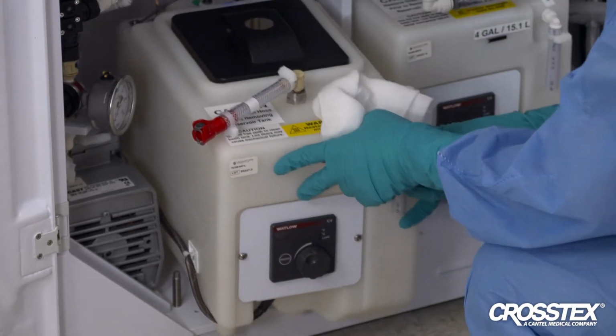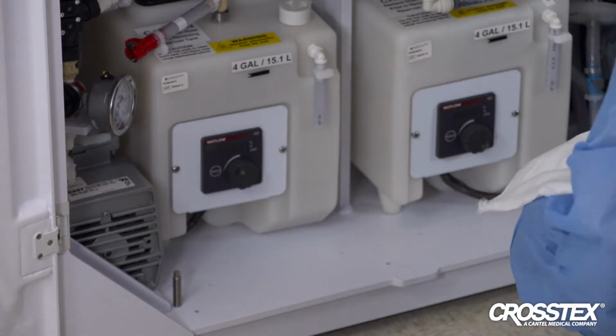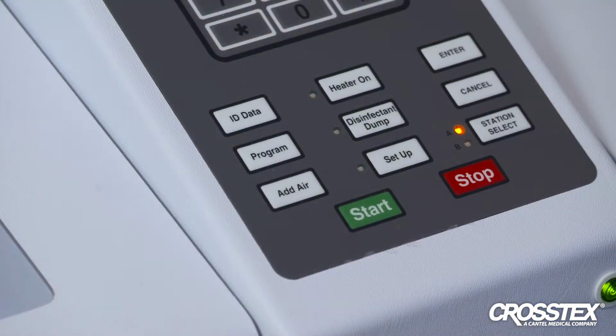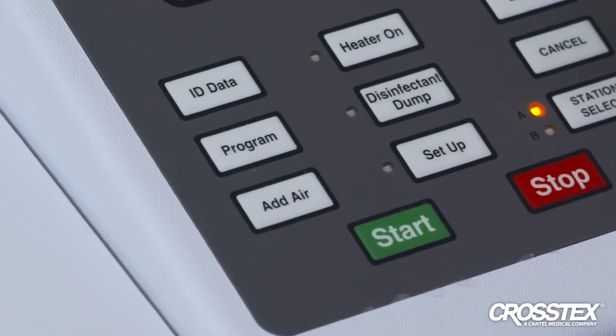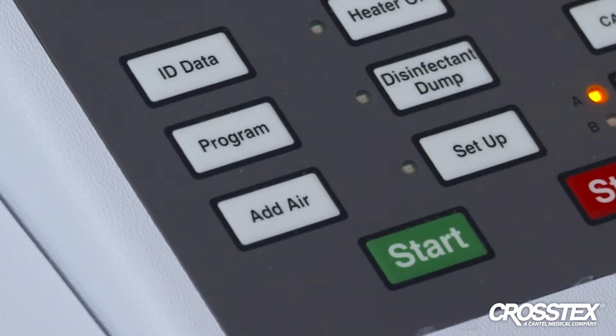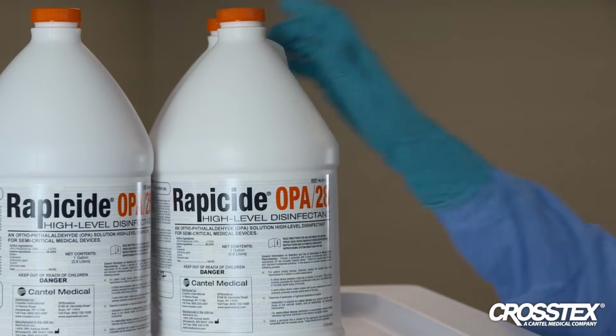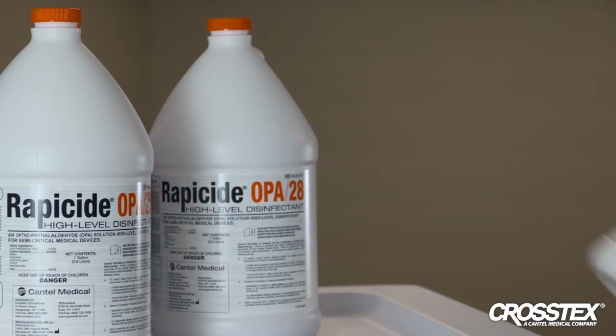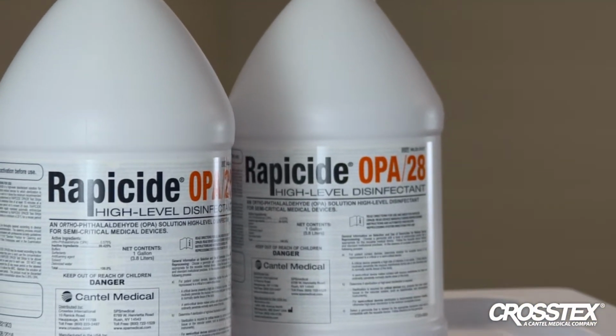Fill the reservoir tank with fresh water. Run 2 standard cycles with the fresh water and dump again, using the same control panel process as before. The Rapicide HLD solution is now ready to be added. Open the bottle of Rapicide OPA 28 high-level disinfectant.